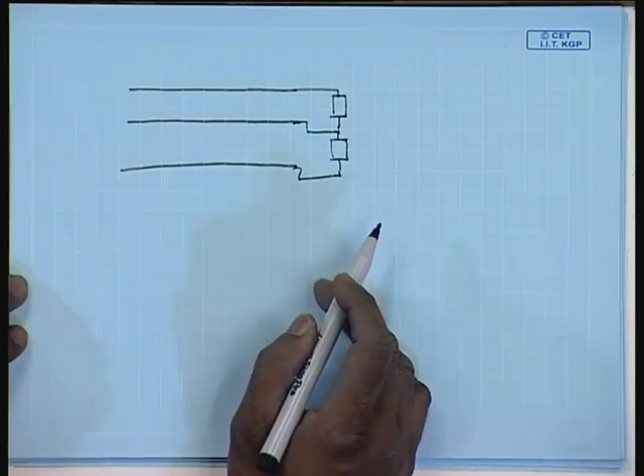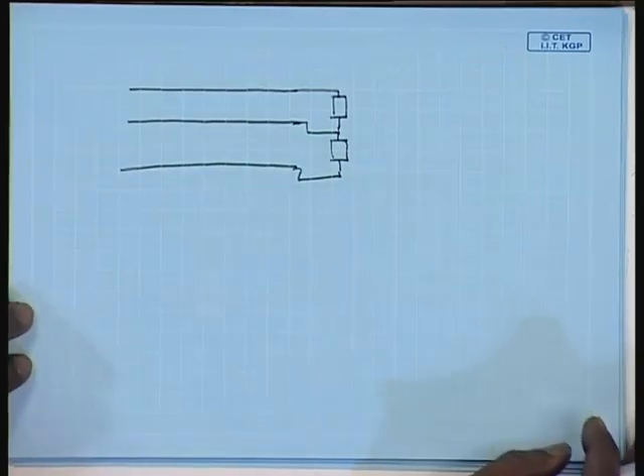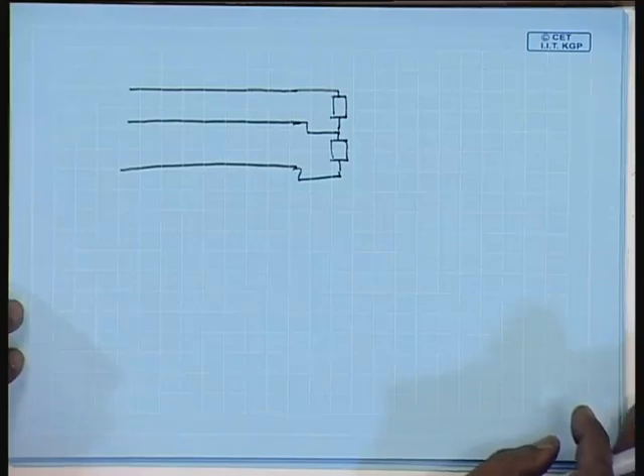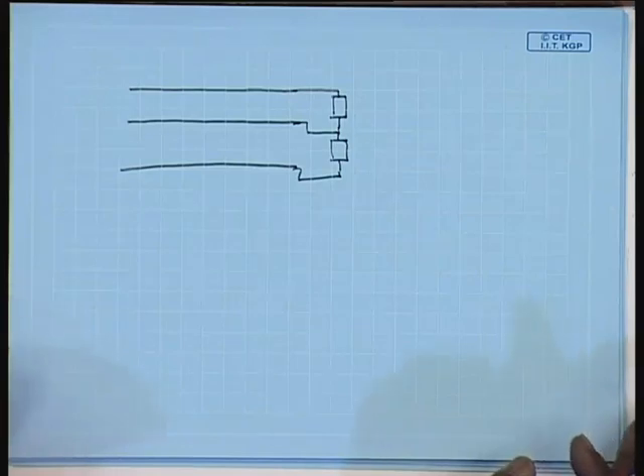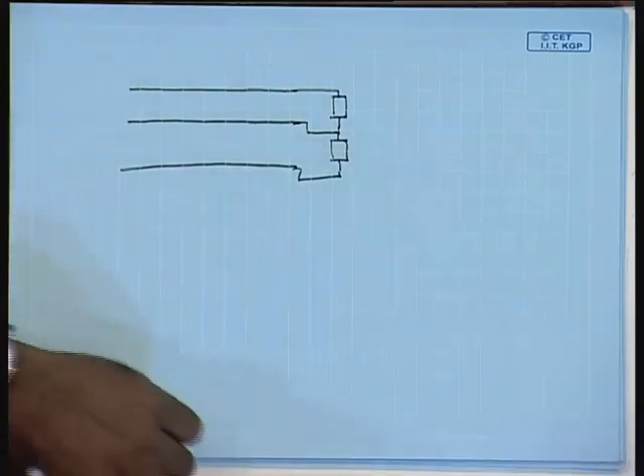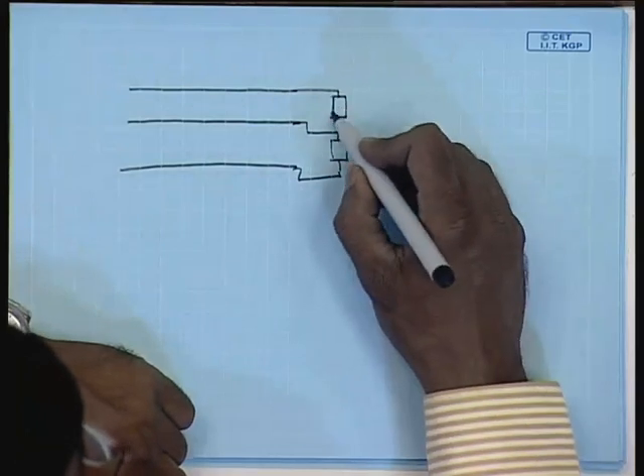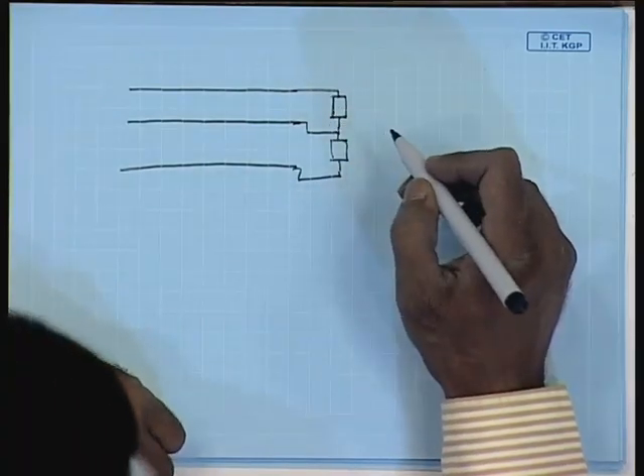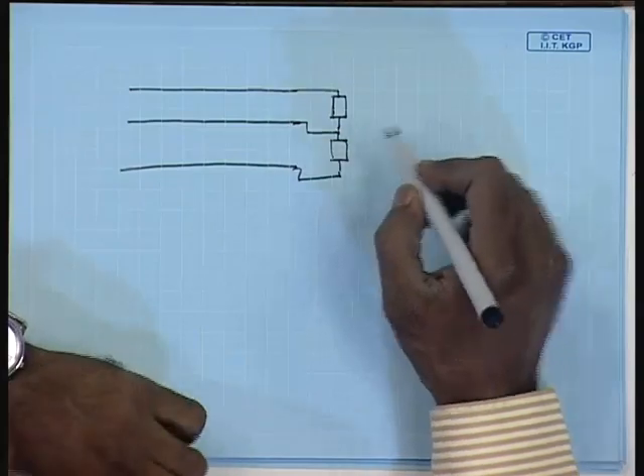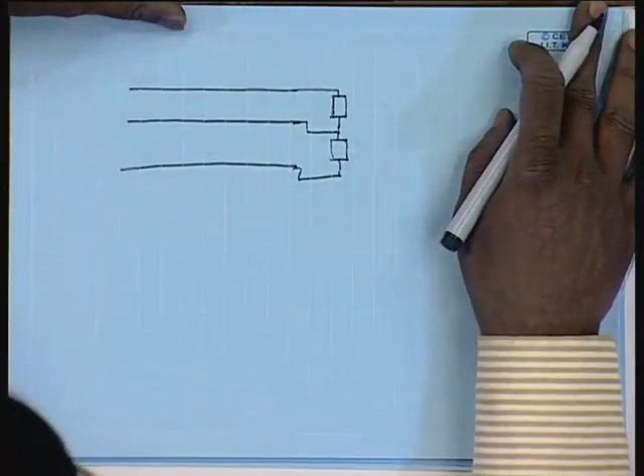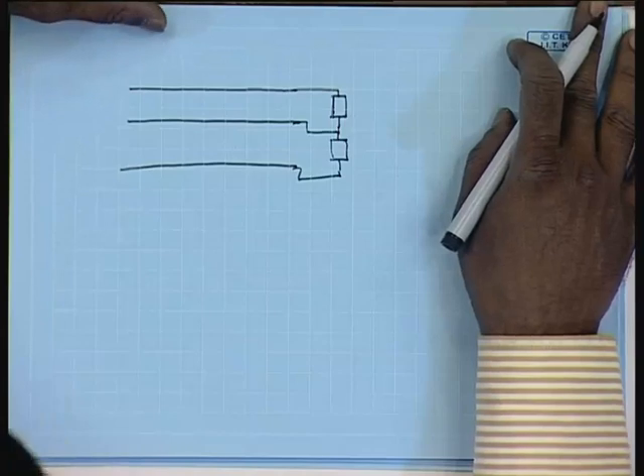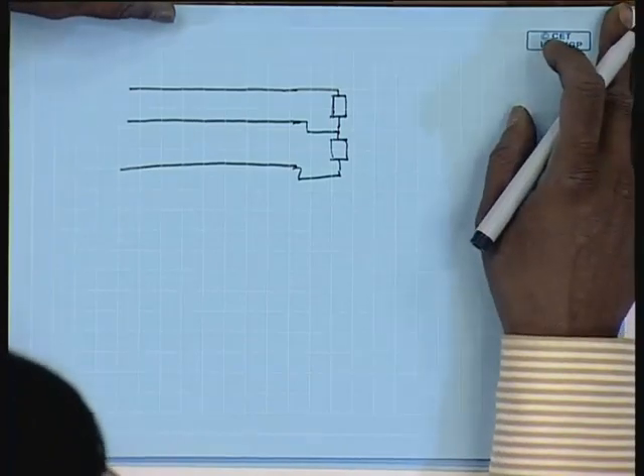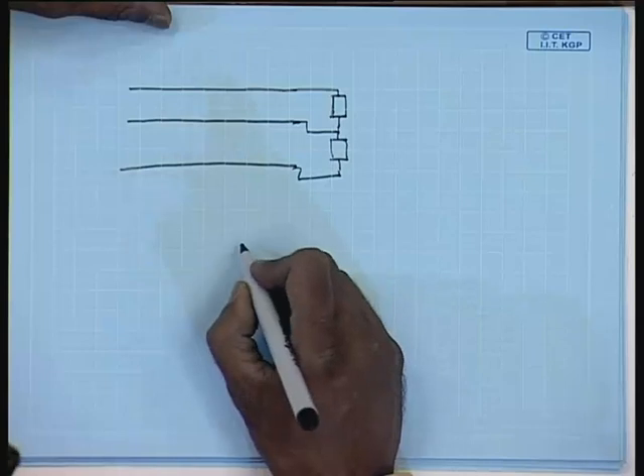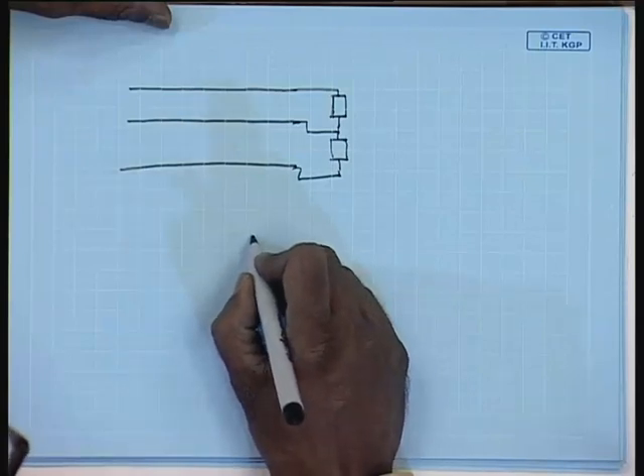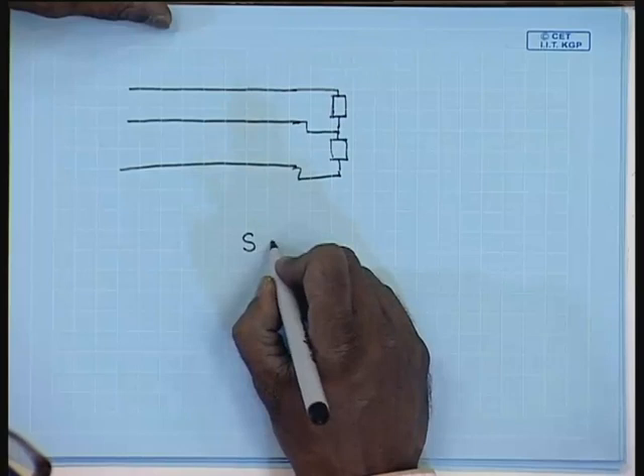Not only that, many two phase loads will require a balanced two phase supply as well. Some of these two phase loads are large arc furnaces or induction melting furnaces, which can range in power up to megawatts. So care should be taken to make sure that the loading of the three phase system is balanced to the extent possible.